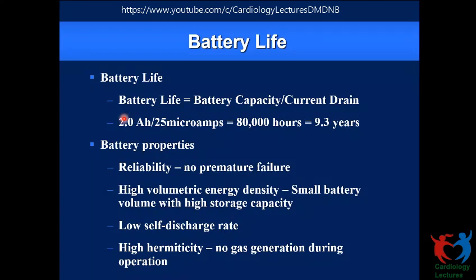So in the current pacemakers, typically the ampere hour is about 1.2 to 1.5 ampere hour. And then the current outgo is not 25 microamperes, it's of the order of 15 microamperes. Let's say 1.5 ampere hour battery, 15 microampere continuous current drain. Then when you divide the ampere hour by the continuous current drain, we know how many hours the battery would last. Then we can estimate the longevity in terms of months or years.